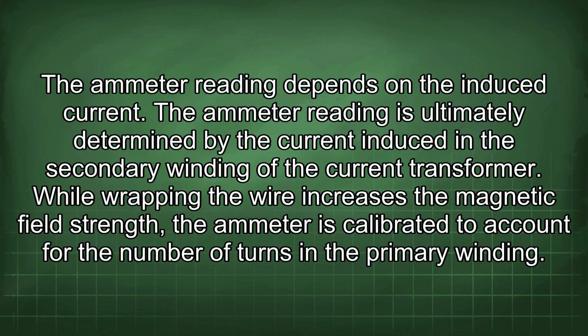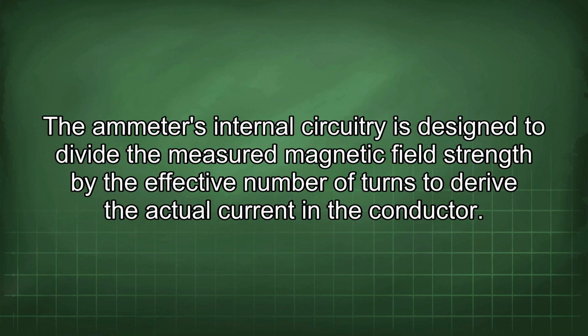The ammeter reading depends on the induced current. The ammeter reading is ultimately determined by the current induced in the secondary winding of the current transformer. While wrapping the wire increases the magnetic field strength, the ammeter is calibrated to account for the number of turns in the primary winding. The ammeter's internal circuitry is designed to divide the measured magnetic field strength by the effective number of turns to derive the actual current in the conductor.